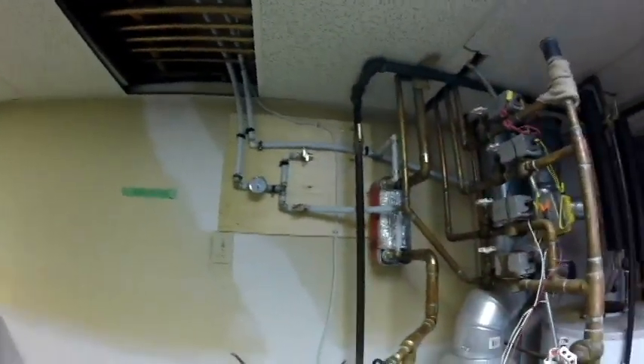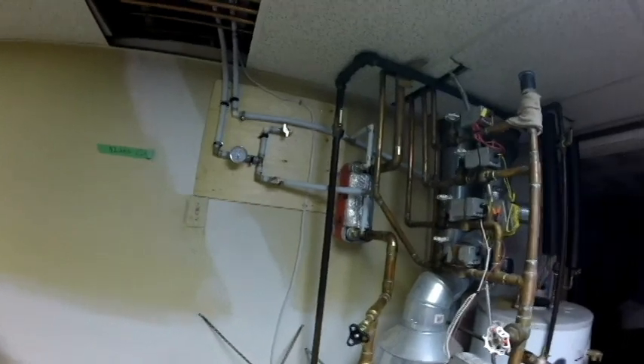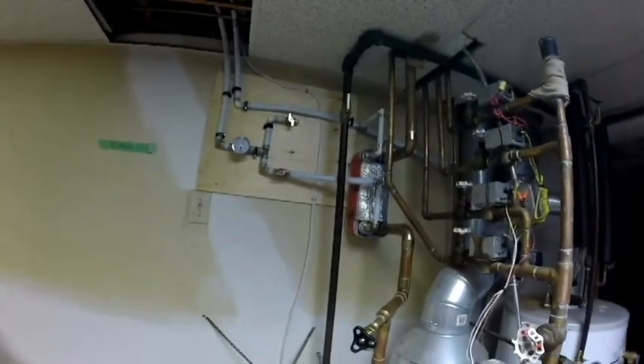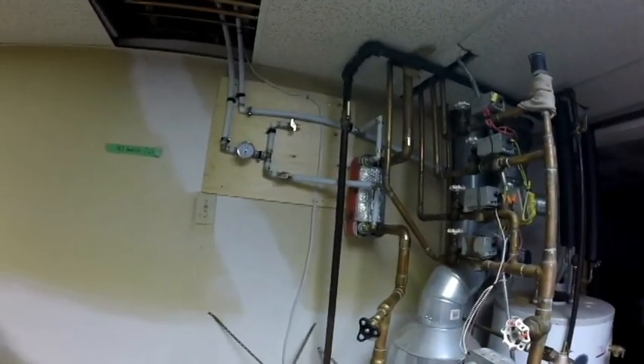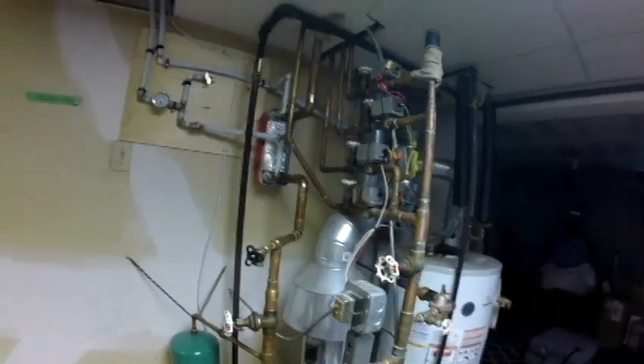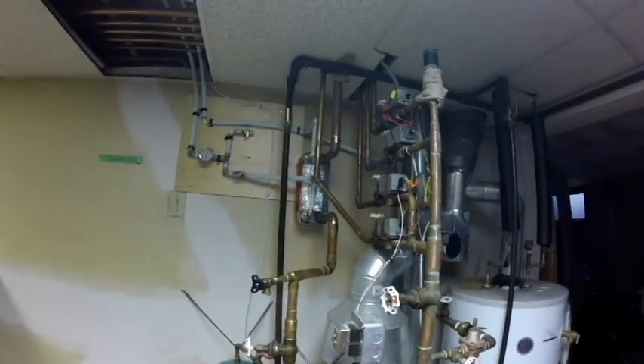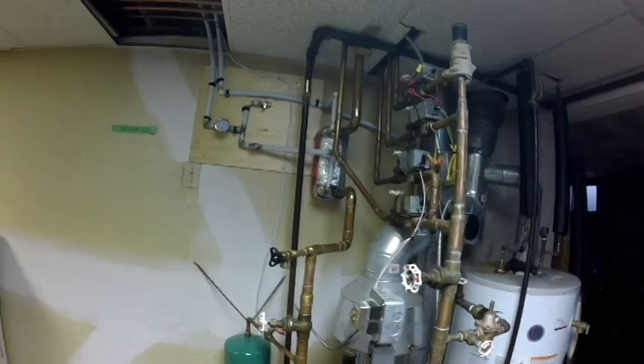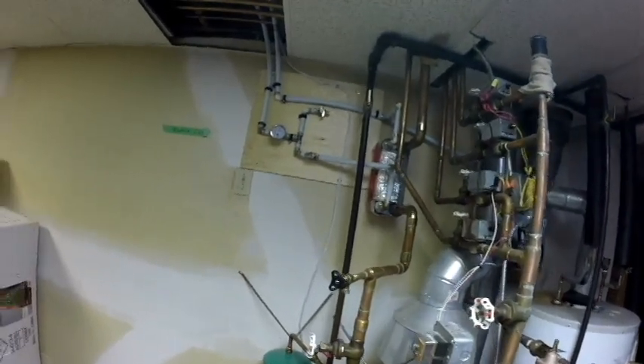This here is the water system coming in. It comes in from the outside, passes through the PEX lines, and the PEX is another thing that I'm not too crazy about. On the output side of my boiler, I'm going to be replacing that with straight copper because the PEX, I don't trust it. I've had a couple of failures already because it can't handle high enough heat consistently.